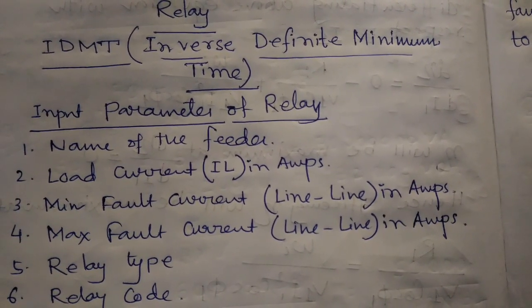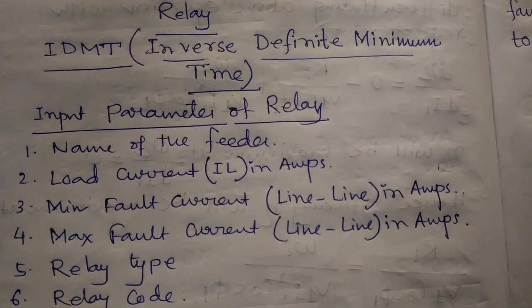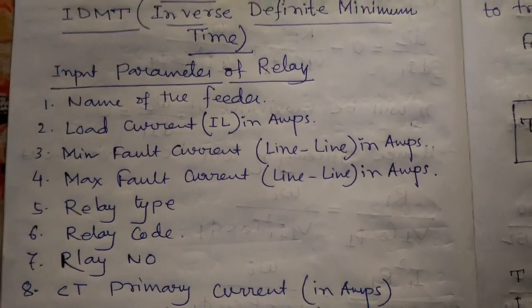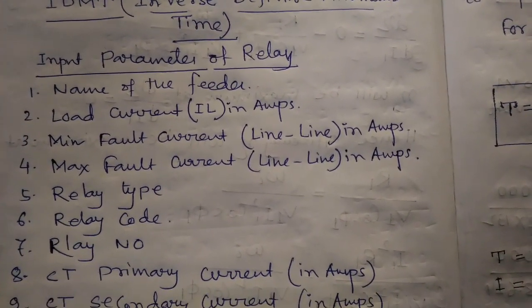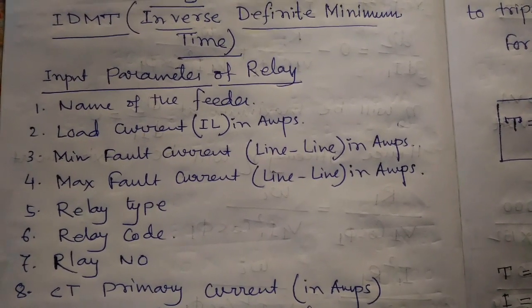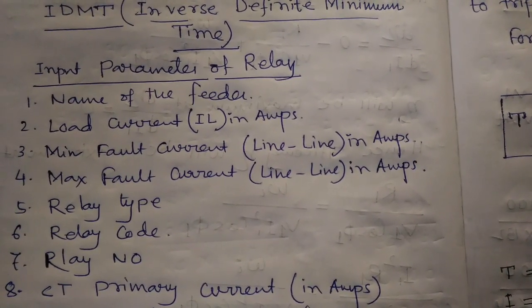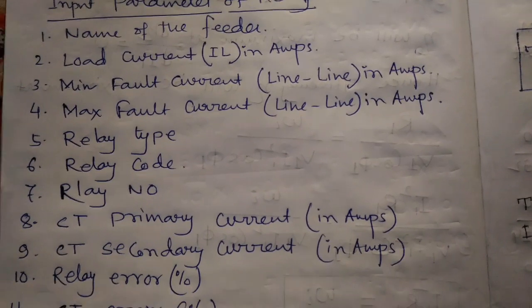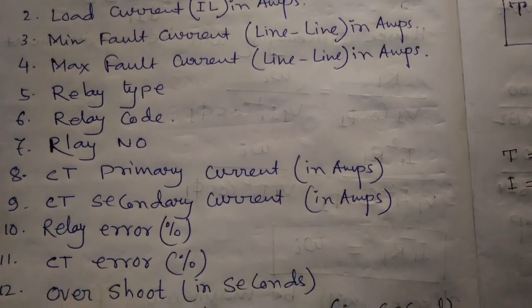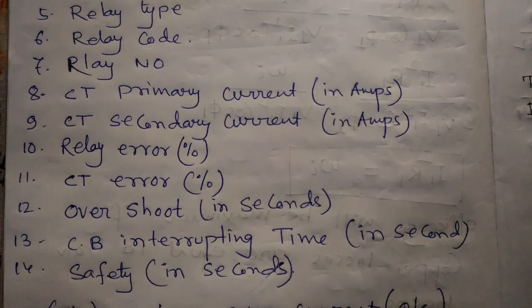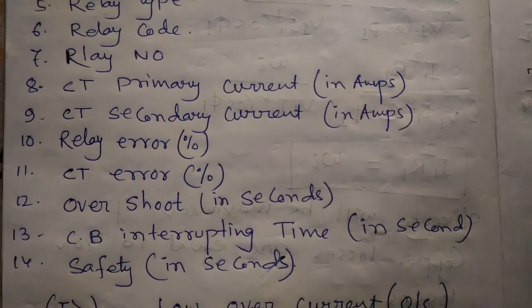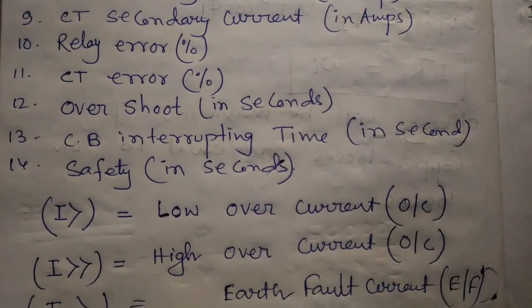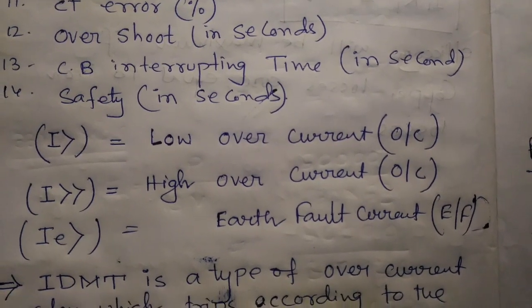Let us start with the input parameters of the relay. The input parameters include: name of the feeder, load current in ampere, minimum fault current line to line in ampere, maximum fault current line to line in ampere, relay type, relay code, relay number, CT primary current in ampere, CT secondary current in ampere, relay error, CT error, overshoot in seconds, circuit breaker interrupting time, and safety.